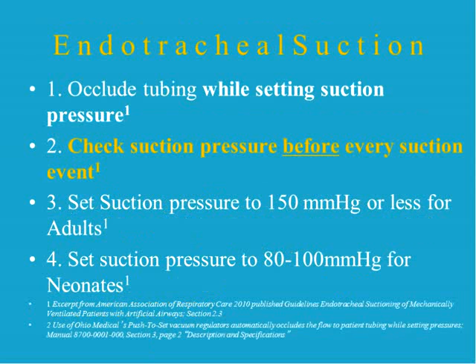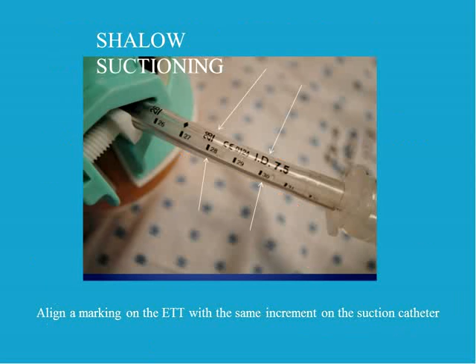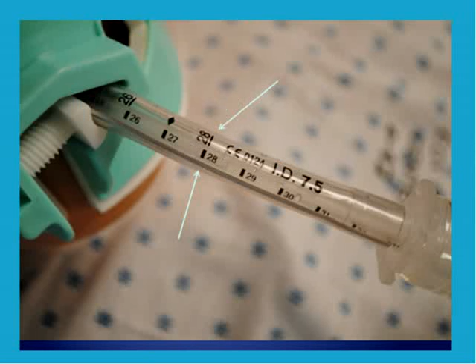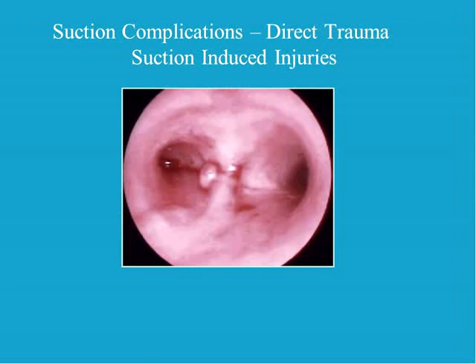So what do we mean by shallow suctioning? Here's an endotracheal tube where the markings on the top of the tube are visible, and you're looking through the tube at the suction catheter, where you'll see those same markings. To shallow suction, one needs only to line up those two markings. In this case, the marking 28 was lined up on the catheter and the endotracheal tube, so that you can be sure you're suctioning at the end of the endotracheal tube. If you don't do that and you deep suction, you could cause injuries such as you see in this picture.